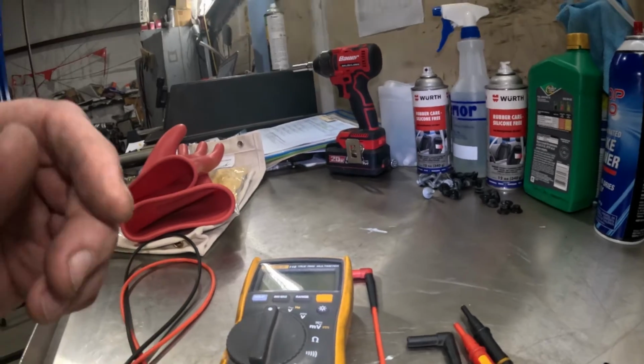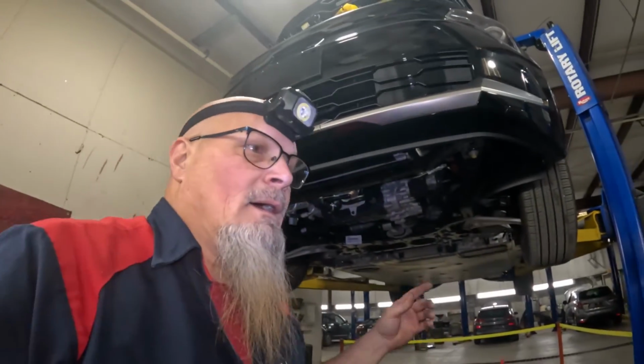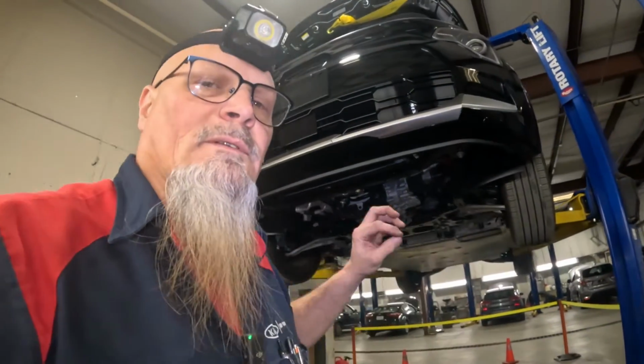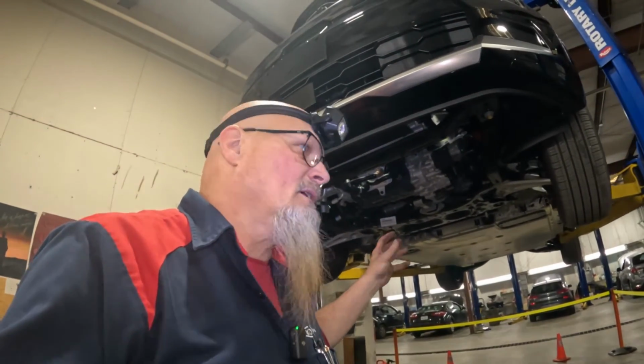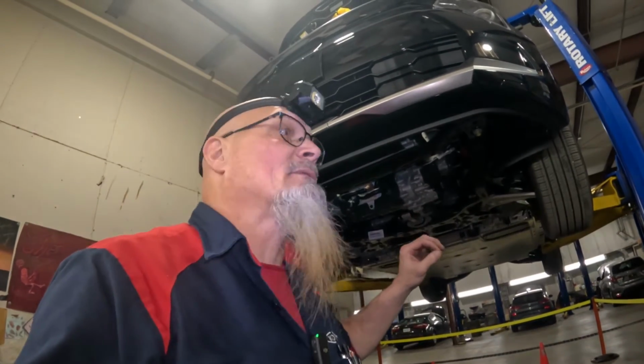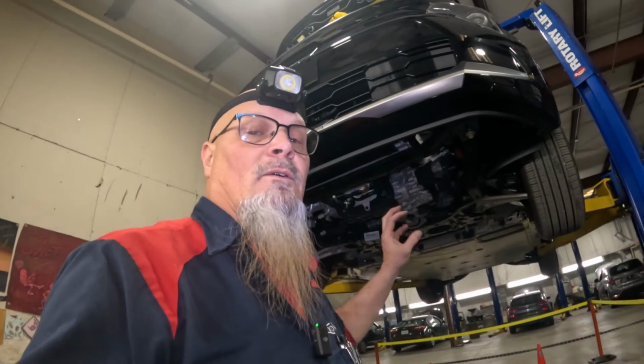It's been well over 10 minutes, so I will get the gloves on and we'll take that off and check to see if we've got any voltage there. We're looking for less than 30 volts - less than 30 volts, we're good. If it's got more than 30 volts, then there's a problem somewhere. So we'll get up there and check that out right now.